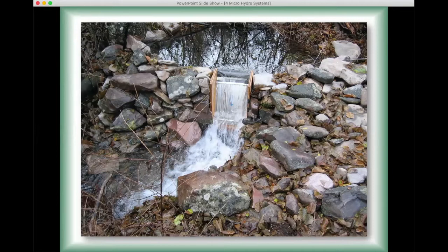Yeah, so this is the Coanda or wedge wire screen that I briefly spoke about. This is the most common one that we use. Essentially it's a self-cleaning screen. So you set it up, damming up the stream basically, and having the spillway be the entry to the pipeline. As the water spills over that wedge wire, it basically shaves it off.